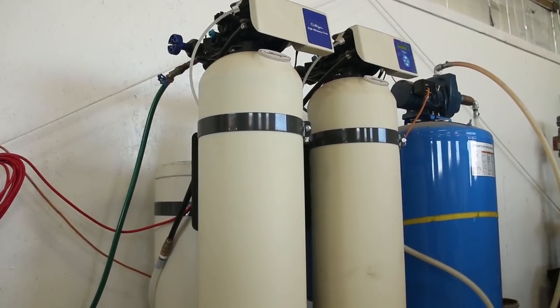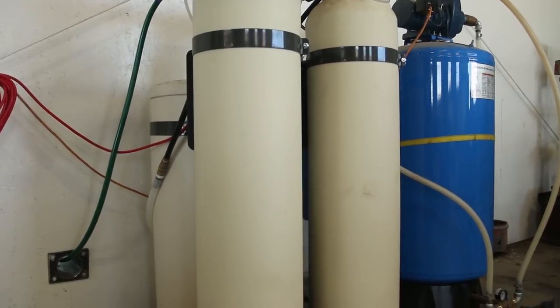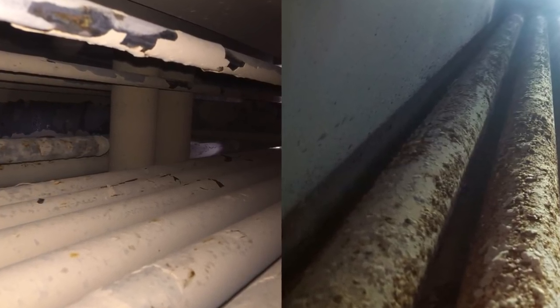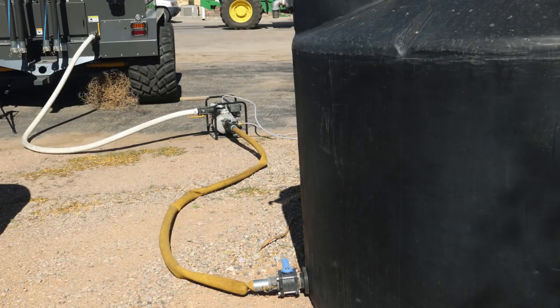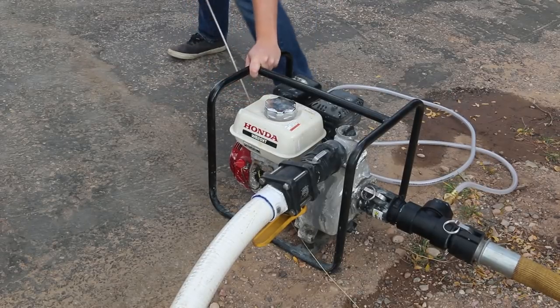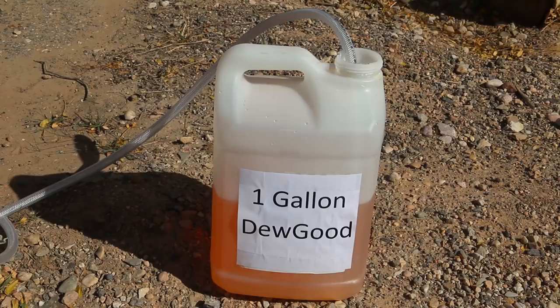Only use soft water or reverse osmosis treated water in the Dewpoint machine. This prevents hard water scale from forming inside the boiler. Add one gallon of DewGood to every 1,000 gallons of water. This protects the steel inside the boiler from corrosion and also ensures boiler longevity.